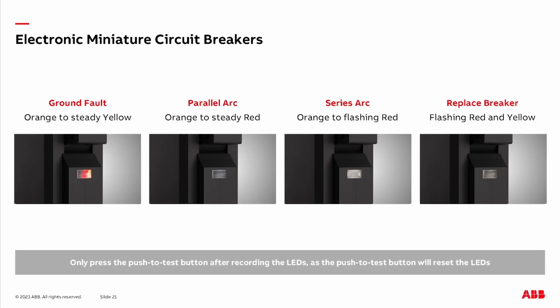The breaker LEDs will begin as orange to demonstrate that the breaker is functioning properly. If the breaker begins orange and then goes to a steady yellow, the breaker has detected a ground fault. If the breaker LED begins orange and goes to a steady red, the breaker has detected a parallel arcing event. If the breaker LED begins orange and then goes to a flashing red, it detects a series arcing event. If the breaker is flashing red and yellow, please replace the breaker.